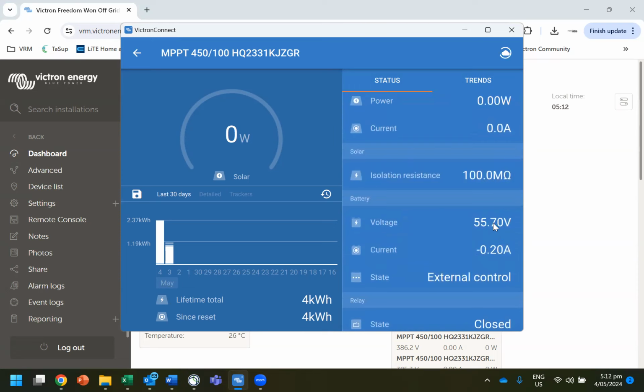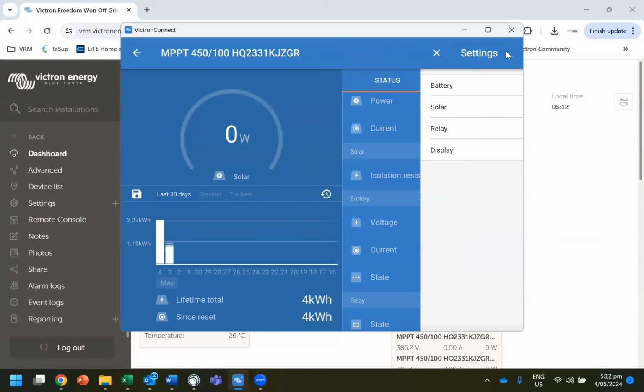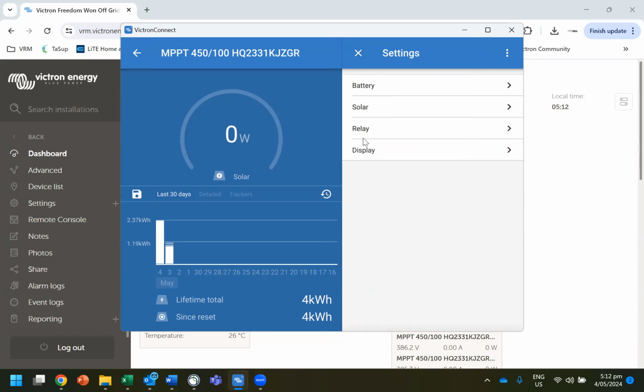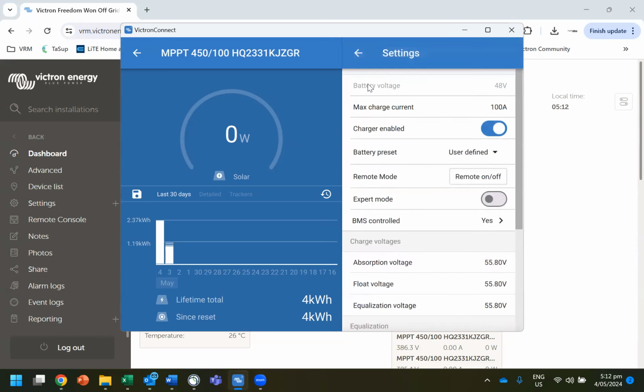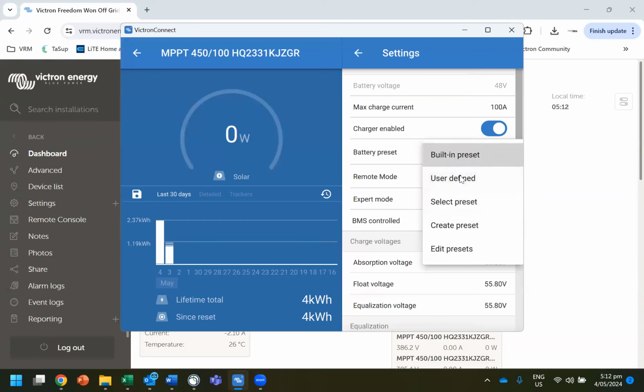And we've got what the battery voltage is. And see here, it says external control. That says that the charge controller is not using its own settings. It's using information from the battery, which is good. You want that in a managed battery system. So now once the settings have loaded, up the right here, we're going to click on this settings. We've got battery, solar, relay, display. Basically, I'm really only interested in the battery settings. And you'll see there that these are all set up correctly. You're going to go from a built-in preset to user defined, which is this one here.